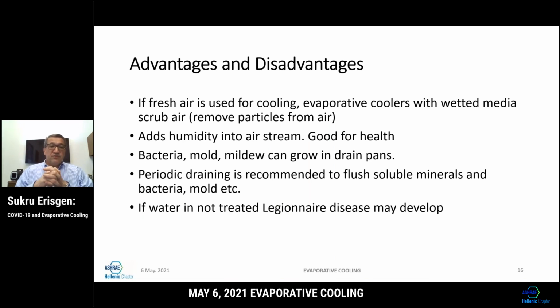So if fresh air is used, evaporative coolers with media can scrub some of these particles from the air and add humidity into the airstream, so it is good for our health. But the negative effect I was mentioning earlier, there are some theories that bacteria, mold and mildew can grow in drain pans. So it is very important to treat the drain pan, either using UV lights or draining them regularly. If the water is not treated, Legionnaire disease may also develop. So we need to be very careful. We don't want to turn something very beneficial into a health disadvantage.